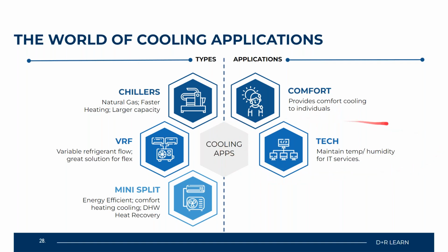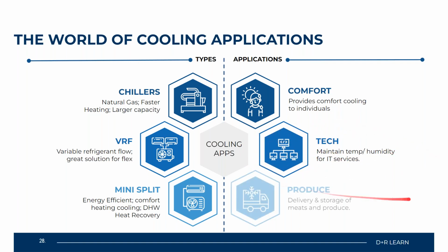Technology. I've worked in the technology department as an HVAC tech in my earlier days, where AC was very, very important in the technology world. During the time that I spent with Amazon, I maintained the cooling for a lot of their data farms. And when we lost cooling, it was a problem because your Netflix went out. So for that short 5 minutes that you lost connection with Netflix, it typically wasn't your internet connection. It probably was a server that happened to go down, but it was brought back up extremely quickly from the work of several professionals on site who worked together to bring those systems back online. And HVAC is one of them. When you have these servers working overtime and generating an extreme amount of heat, they can burn out if you don't have an adequate amount of cooling.